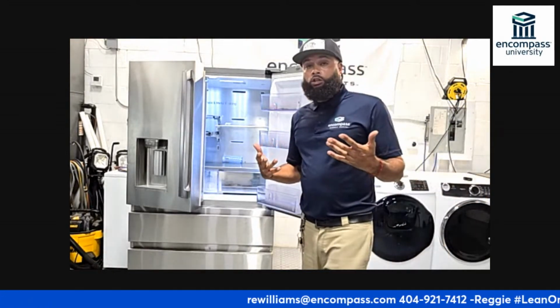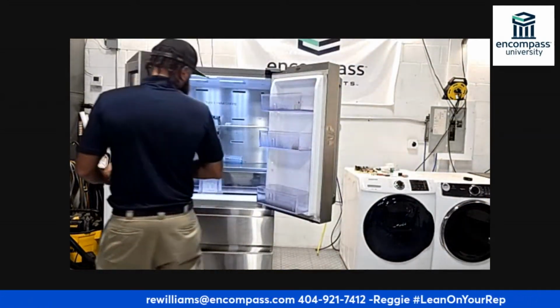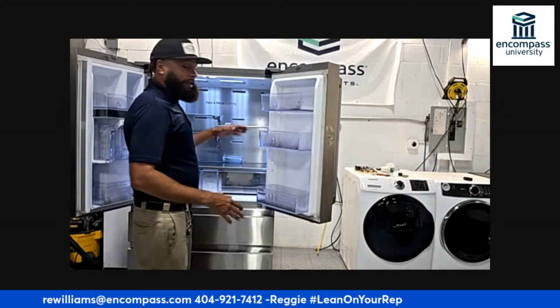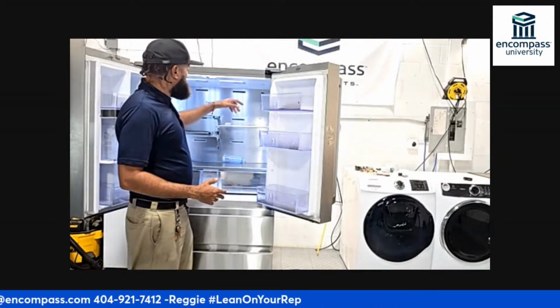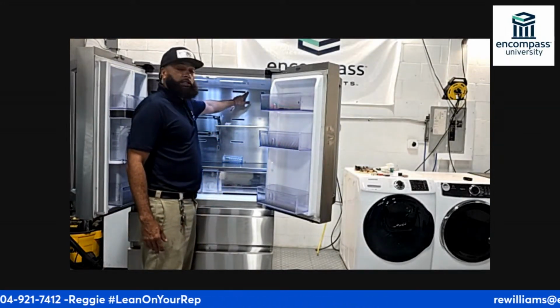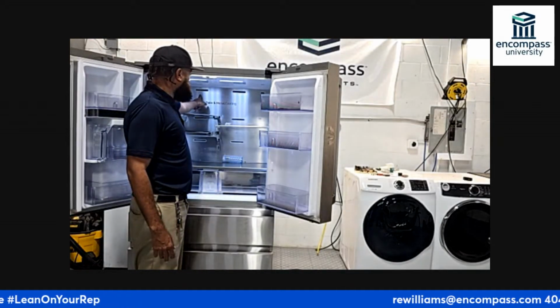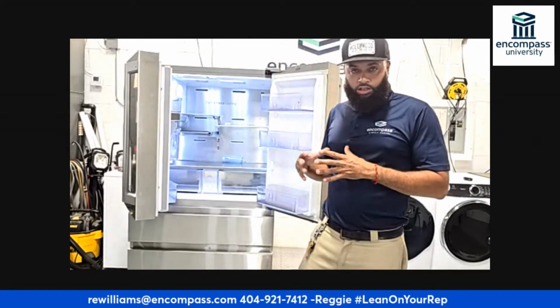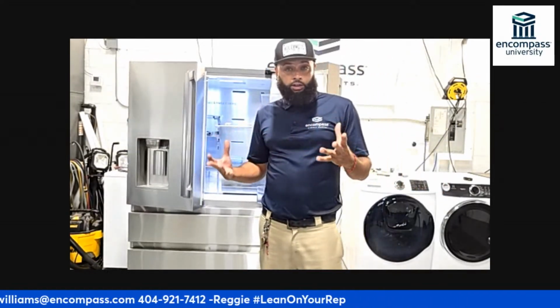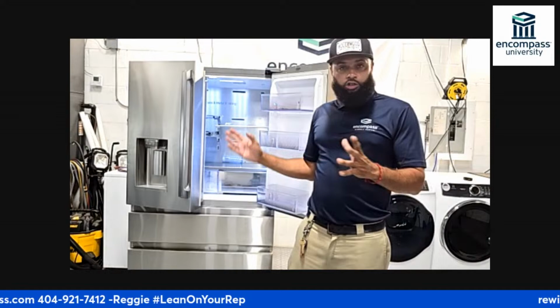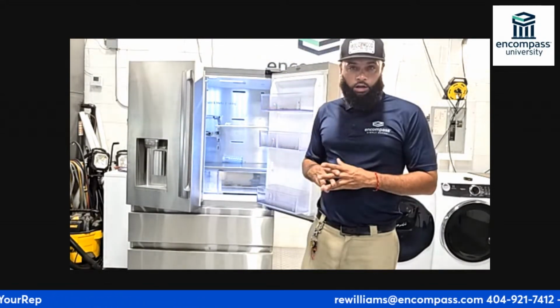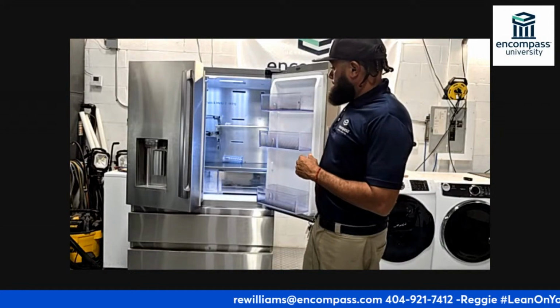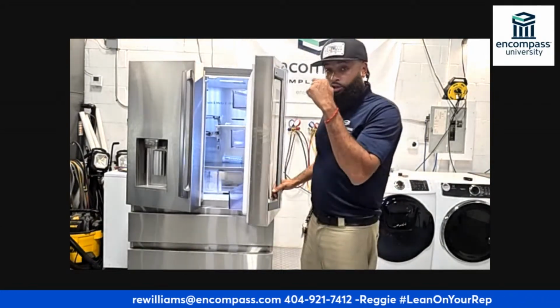Another test I want to do is look at my cover. I know Samsung in particular is notorious for icing up in these little covers, these little ports. I want to make sure they're free of ice, that I don't have a defrost issue going on, and that my ports are clear — not an iced-up evaporator cover. That's what I'm looking at in this compartment.